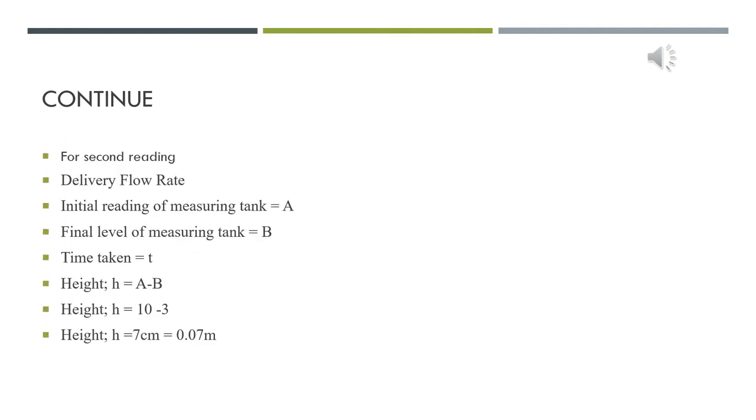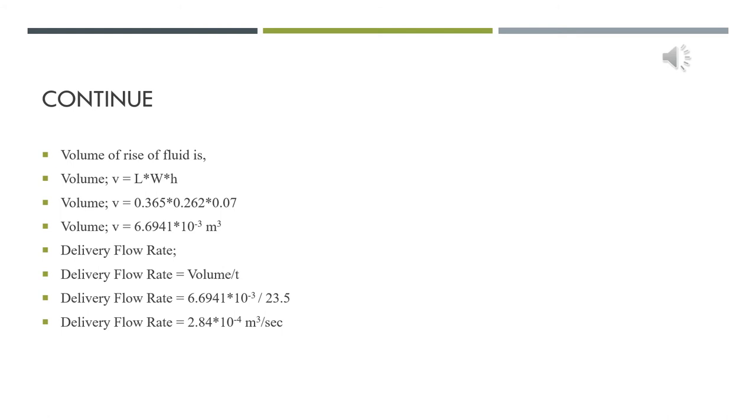Take the second reading for calculation. First, we have to find the delivery flow rate. The initial reading of measuring tank equals A and final level equals B. The time taken equals T. The height H equals A minus B. The height equals 10 minus 3 equals 7 cm or 0.07 meter. The volume of the rise of fluid equals length times width times height, which equals 6.6941×10⁻³ m³. The delivery flow rate equals volume divided by T equals 6.6941×10⁻³ divided by 23.5 equals 2.84×10⁻⁴ m³ per second.